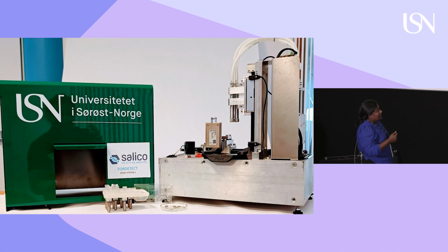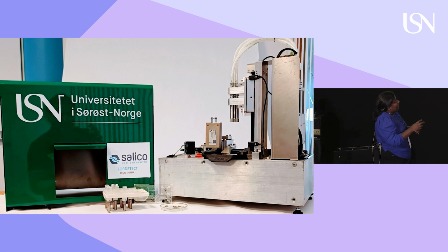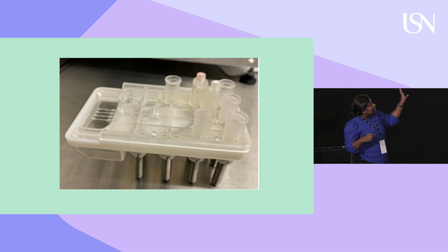If you see this, it looks like a single instrument, but it has multiple disciplines in it to make it functional. We have electronics on board, the fluorescence overhead, the outer system, and everything. Finally, this is the heart of the system. We call it a Salico cassette. The cassette is covered by a top and bottom layer. Inside, the chip is made on a lab-on-chip theme.